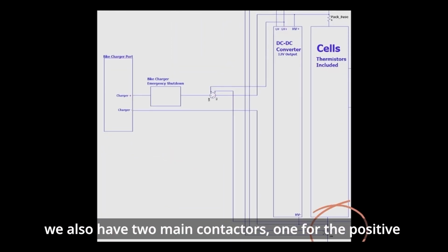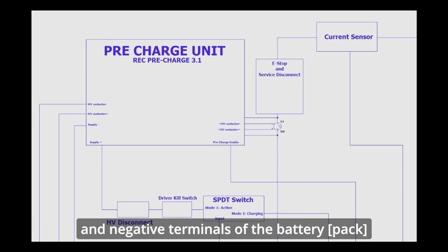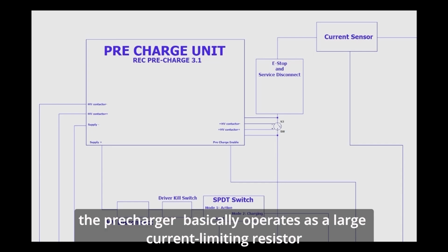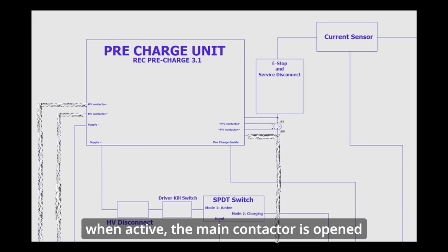We also have two main contactors, one for the positive and negative terminals of the battery. The precharger basically operates as a large current limiting resistor. When active, the main contactor is opened and current flows through the precharger. When it finishes, it closes the main contactor, allowing for full current flow to the motor.